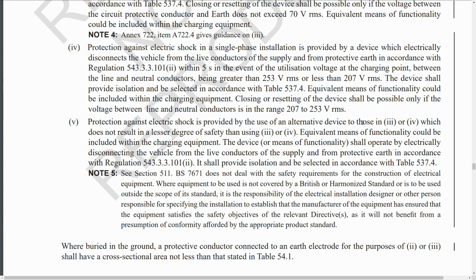Now, in principle, this is a good idea because generally, if you have a TN-C-S supply and the PEN conductor, that's the combined earth and neutral conductor, is damaged, then what tends to happen is that the voltage between the line and neutral will go outside of this range in some circumstances. And of course, the most dangerous part of that is that the voltage on what was the earth conductor or the protective conductor actually becomes fairly high in relation to the actual earth itself outside.